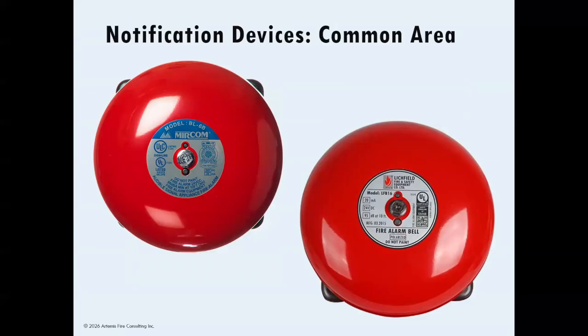Secondly, we have notification devices, which will alert residents of an emergency situation. The current building code requires adequate notification both in the common areas and in suites. We'll start with the common areas first. We're all familiar with the traditional bells shown in the picture. The challenge with them, though, is that they don't often provide the code-required decibel levels inside of suites, meaning folks in the far end of the hall or whose bedrooms weren't close to the bells often couldn't hear them at all.